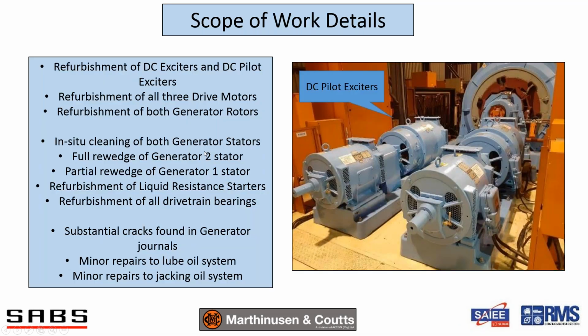Okay, a little bit more detail for the rotating machines people here. It was the refurbishment of the DC exciters and DC pilot exciters. So all old DC machines with commutators, old but very reliable. The refurbishment of all three drive motors. Now, those of you who know rotating machines, I think in my time I've seen 3 2-pole 50 hertz wound rotor induction motors. Remember that they have to have their rotor winding supported from centrifugal force. So they're very special machines. And it's amazing how well they operate, and how when you witness this plant running up the first time after recommissioning, you're in a sweat afterwards. Then you get to sort of 2 weeks later, and Seth ends up starting these drivetrains as if he's starting his car. So it's really reliable stuff.